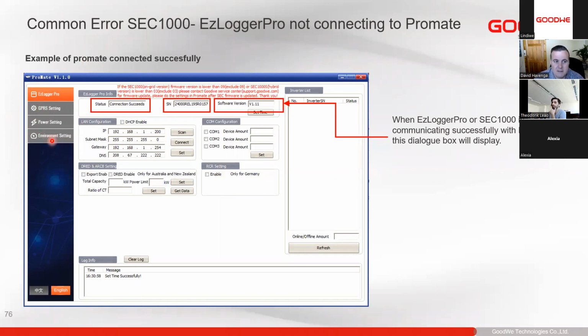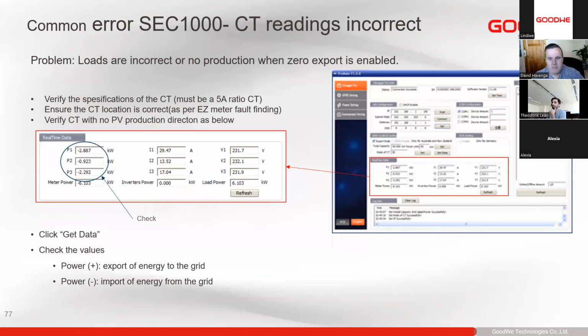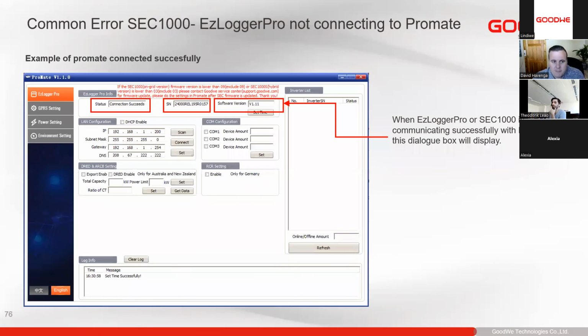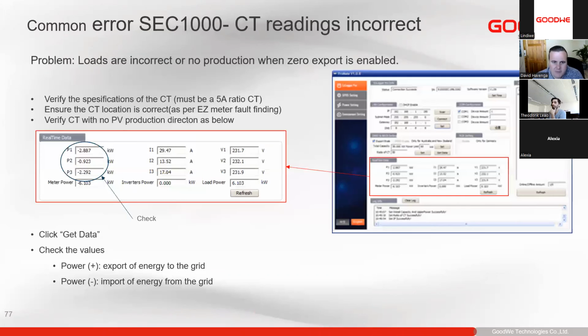Generally, anything we need to set is on this first page. We don't need to set anything in power settings, because most of this will be configured over here. Next, if you want to see load data with the SEC1000, we enable this export enable button here. Then we can fill out all the required information below. Thereafter, we can check whether our CTs are working correctly.